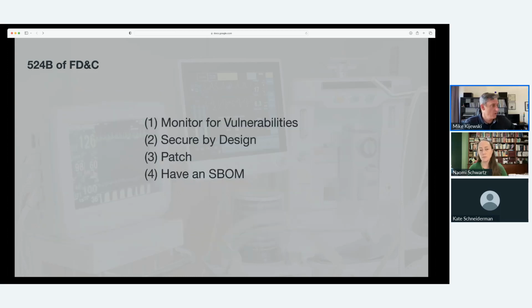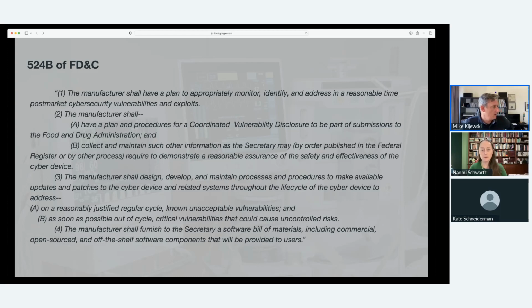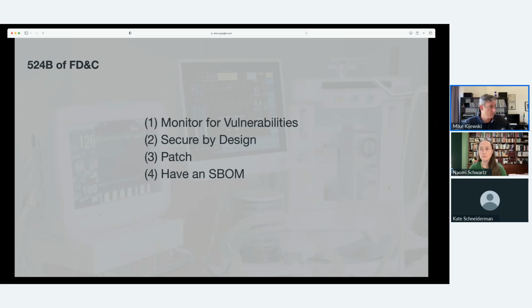But essentially, it boils down in my mind to four things. Number one, device manufacturers should have a process by which they monitor for vulnerabilities in their medical devices, right? Number two, device manufacturers should be building devices that are secure by design, right? There's language in there that says, collect and maintain such other information as the Secretary may require to demonstrate a reasonable assurance of the safety and effectiveness of the cyber device. So ensure that as these devices are designed, cybersecurity considerations are being made, and the regulatory submission provides evidence that the cybersecurity risks of this device have been identified and have been mitigated.